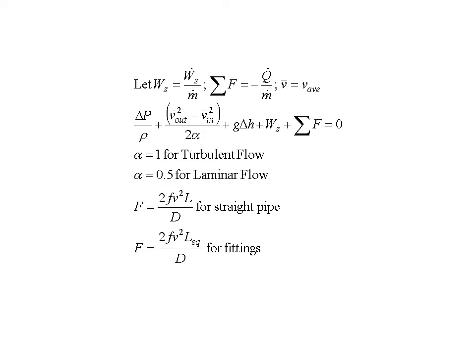Now, for a straight pipe, F is given by the formula 2 times the fanning friction factor times the velocity squared times L divided by D, where L is the length of the pipe and D is the diameter. And for various fittings, we will have the same formula for F, except now we'll use an equivalent length term for that frictional factor.